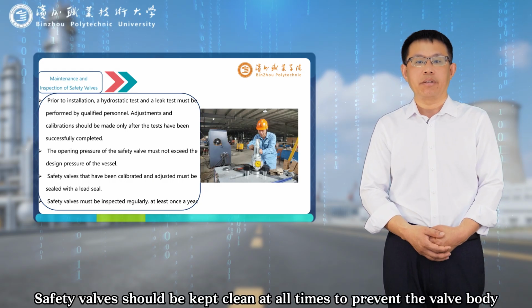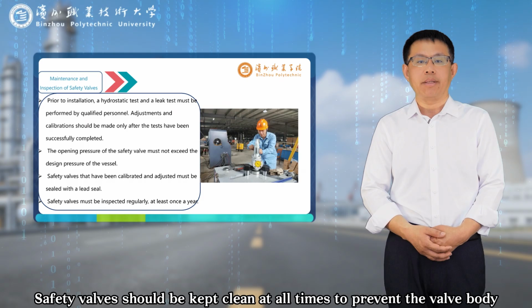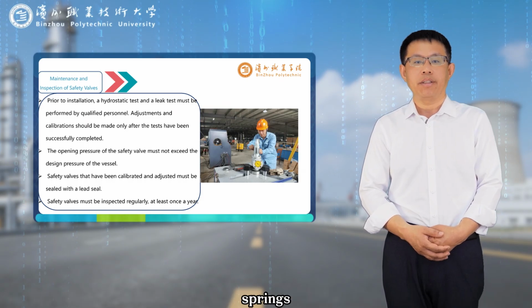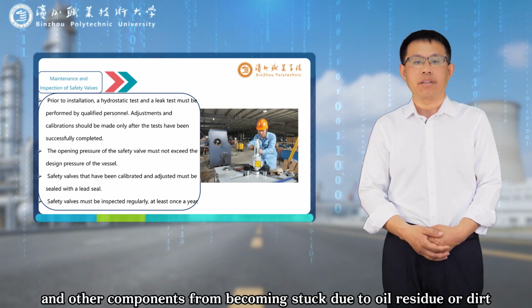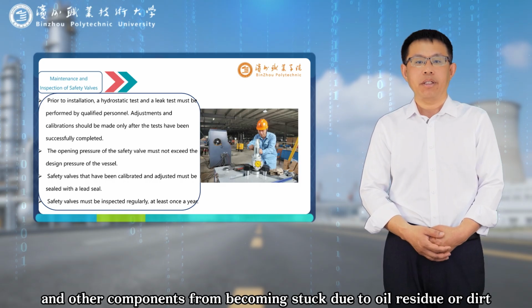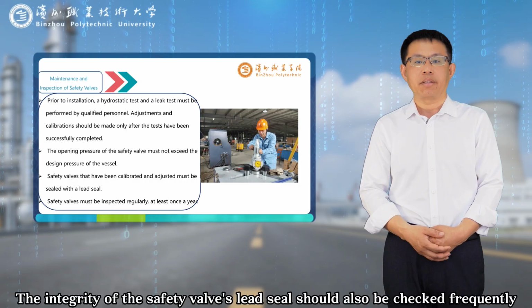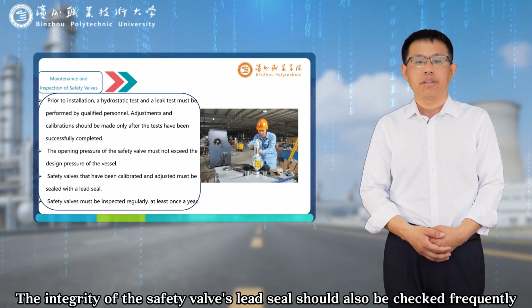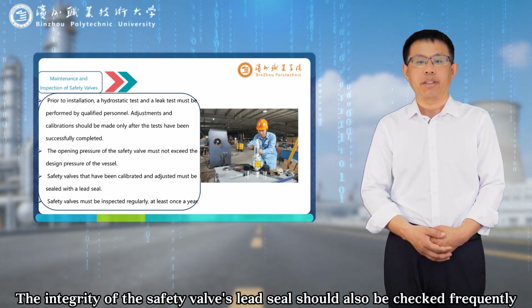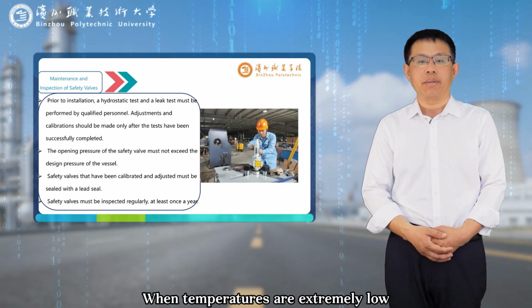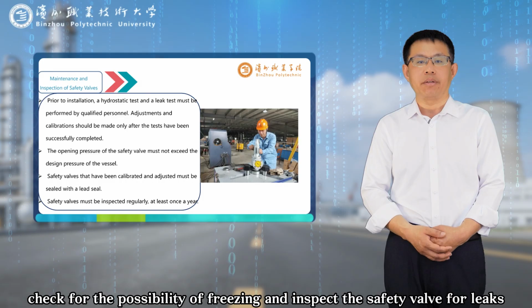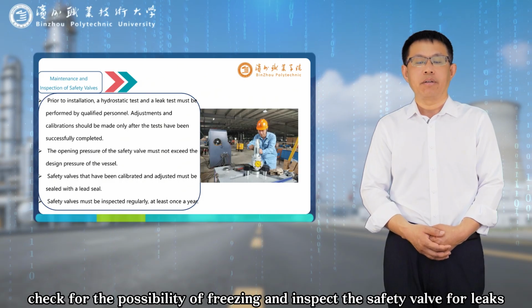strengthened. Safety valves should be kept clean at all times to prevent the valve body, springs, and other components from becoming stuck due to oil residue or dirt, or from being corroded. The integrity of the safety valve's lead seal should also be checked frequently. When temperatures are extremely low, check for the possibility of freezing and inspect the safety valve for leaks.